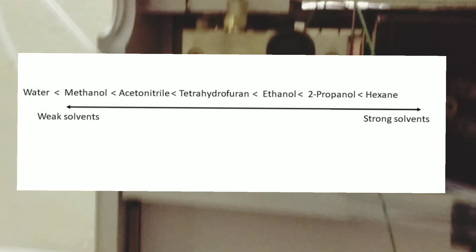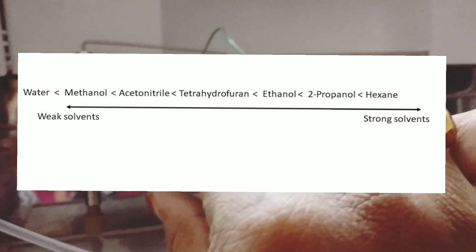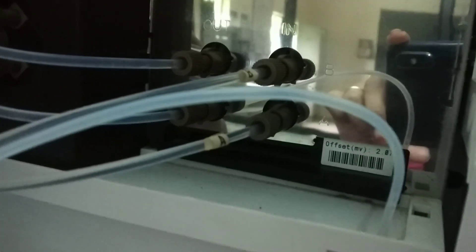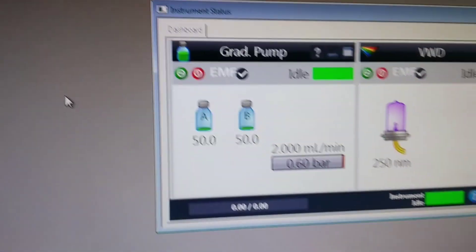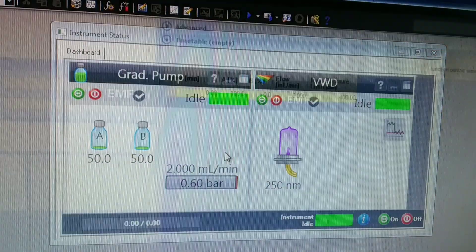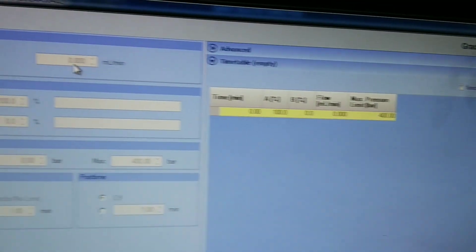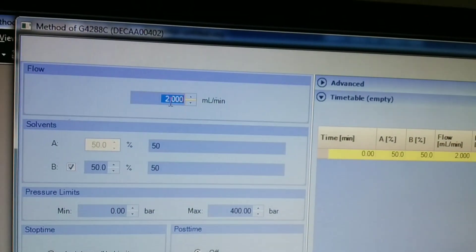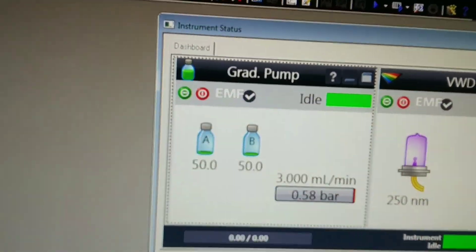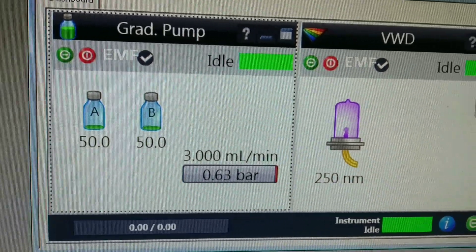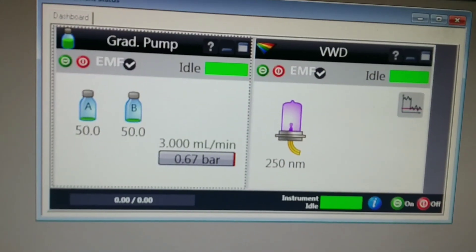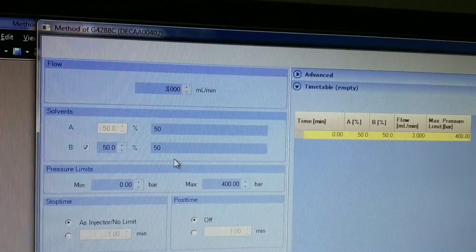You can see I am now closing the purge valve. Now the solvents move into the column and washing of the column starts. You can start the flushing with a combination of weaker solvents, and if it is insufficient, then you can move on with combinations of stronger solvents for washing purpose. We can continue washing with each set of solvent combinations, and if insufficient, we can switch to a new combination of stronger solvents and continue purging and washing with slight increments in the flow rate.